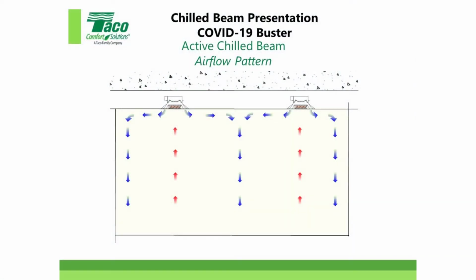And like I said, that's why in our big classroom we have nine of those beams, and they're all spaced properly, so the air comes down and gently falls down into the room. Our ceiling isn't this high, it's probably half as much, at least 12 feet anyway. It's stadium seating, so it might be 16 down by the instructor. Nonetheless, there's your operating principle for the active chilled beam. Here's what you could expect in the flow pattern in a room with more than one chilled beam. Pretty straightforward, pretty gentle, very quiet. No fans, no moving parts.